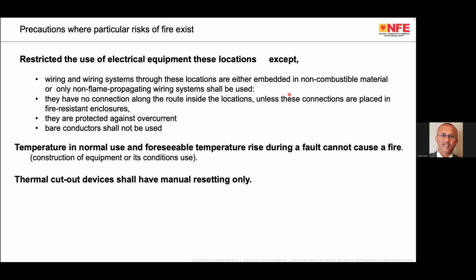Let me tell you an example. Several of the industrial or medical areas, let's say hospitals, where the risk of fire is high. One of the recommendations of the standard is you are not supposed to use bare conductors. Example, the protective earth conductor. In India, we have the habit of using galvanized iron strip as protective conductor all over the plant. If you use GI strip, which is having joints, bolt nut joints, in this particular area, it's a violation of the standard. You are not supposed to use bare conductors. Better is to use a continuous conductor, a fifth wire for this particular application. Temperature in normal use and foreseeable temperature rise during the fault cannot cause a fire, because then you have to have safety measures. Thermal cutout should be manual reset only. These are some of the safety measures recommended in locations where chance of fire is more.